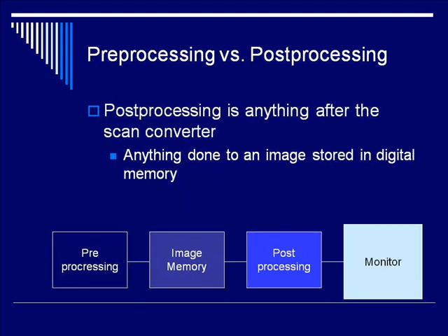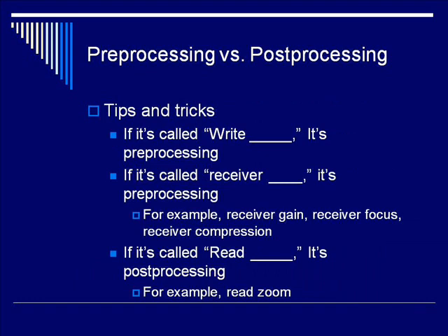Post-processing is anything that happens after we're done with the scan converter — we've stored an image in memory and now we're manipulating it. This is a confusing area, so here are some tips: if something is called 'write anything,' it's pre-processing, because 'write' means writing into memory. If it's called 'receiver anything' — receiver gain, receiver focus, receiver compression — it's pre-processing, as these happen before the image is written to memory. In contrast, if something is called 'read anything,' it's post-processing.